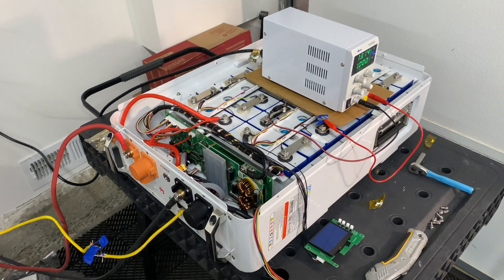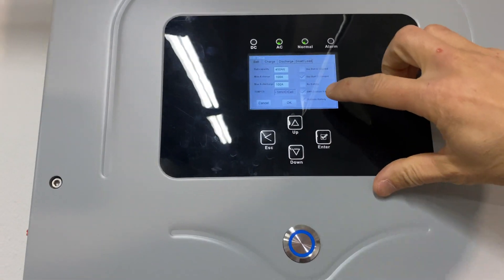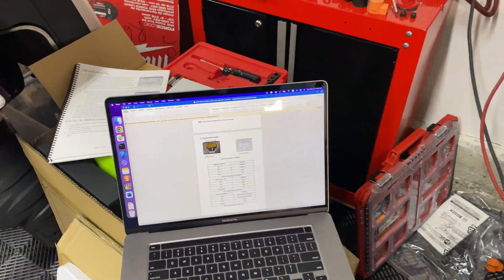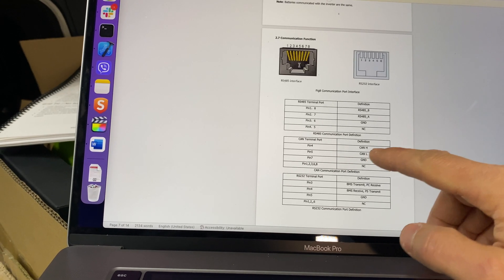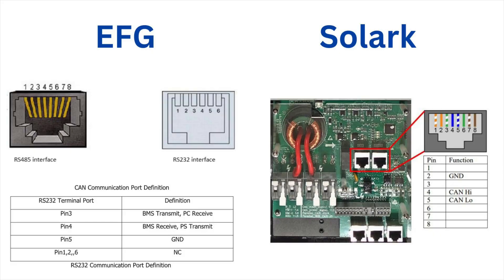Now I'm going to test communication between the battery BMS and the Sol-Ark inverter. I connected this Ethernet cable to the Sol-Ark battery CAN bus port. In the Sol-Ark, we go to battery setup and enable BMS lithium battery, and after that we can read lithium battery information from the battery. At the first attempt it didn't work, so I went to documentation and found that on this battery the CAN bus uses pin number four and five for communication and pin number seven for ground. I had to cut the cable and redo the connections. After doing that, it did work.